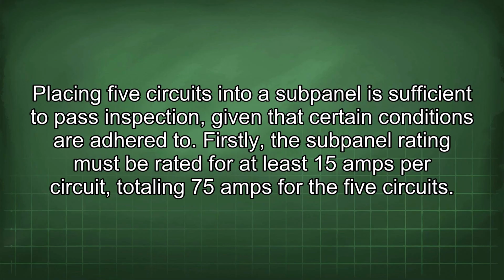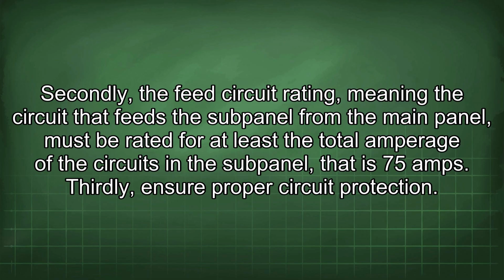Placing 5 circuits into a subpanel is sufficient to pass inspection, given that certain conditions are adhered to. Firstly, the subpanel must be rated for at least 15 amps per circuit, totaling 75 amps for the 5 circuits. Secondly, the feed circuit rating, meaning the circuit that feeds the subpanel from the main panel, must be rated for at least the total amperage of the circuits in the subpanel, that is 75 amps.